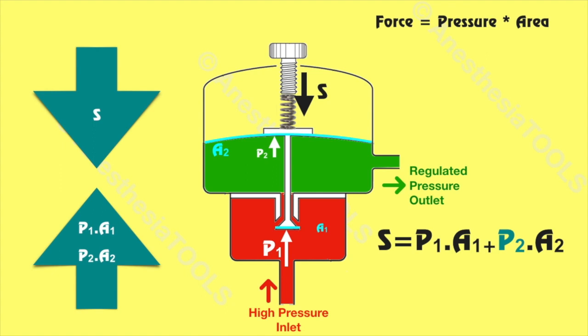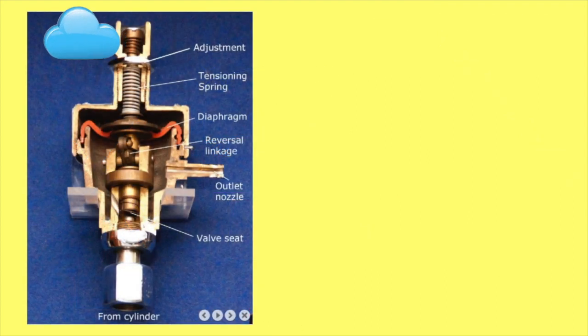Note that if S remains constant, as P1 falls, P2 — the regulator pressure — should rise. So as the cylinder empties, the regulator pressure increases. In fact, as P1 falls, valve V will have to open further to permit the same flow rate. The spring expands, its compression is reduced, and similarly the tension in the diaphragm is reduced. Therefore, as cylinder pressure falls, there is a small reduction in S which partially reverses this effect.